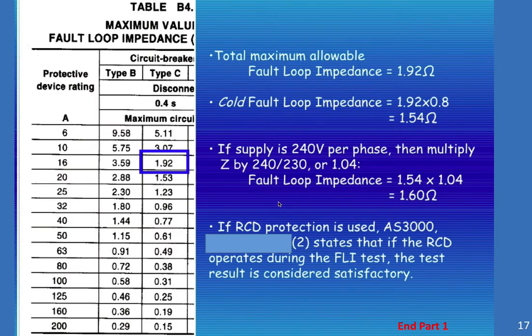If RCD protection is used, AS3000 states that if the RCD operates during the FLI test, then the test result is considered satisfactory. So if you're using a residual current device that is an earth leakage circuit breaker and it trips during the process, then we're happy with that because it has tripped. That's what's important.